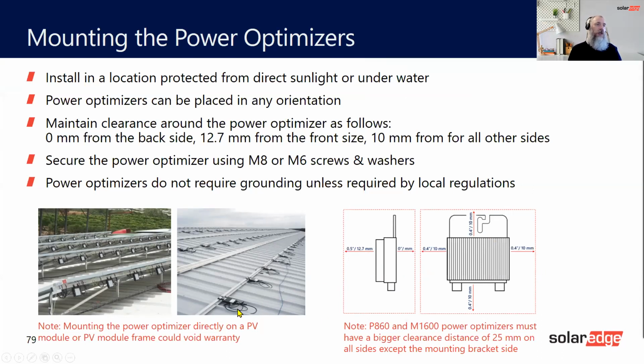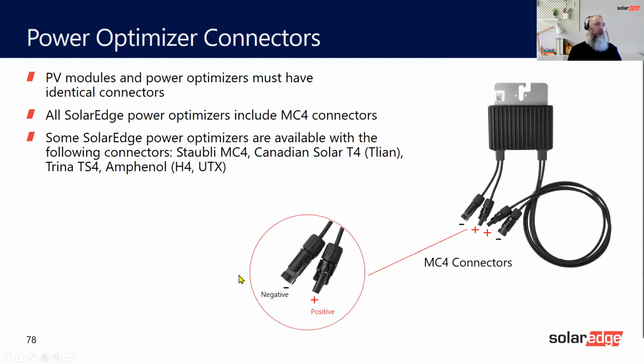If you are connecting the optimizers to your rail or to your roof and you're not fitting the modules down, please make sure that you connect the strings together. So all the MC4s should be plugged together. If we go back to here, the two short ones you can actually plug together. So if you're leaving them over the weekend without putting modules on, these are the string ones, they get plugged together to form your string. It won't do any harm at all.